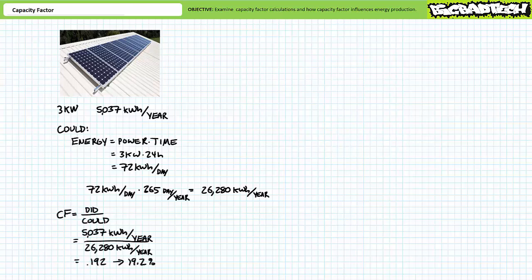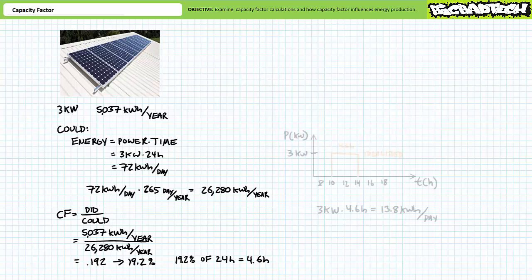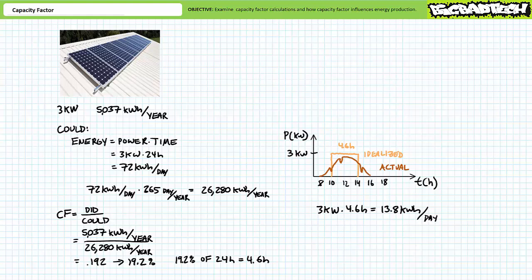Capacity factors did over could. 5,037 kilowatt hours over 26,280 kilowatt hours, its capacity factor of roughly 19.2%. This implies that the solar array produces enough energy as if it did run at full capacity for 19.2% of a day or roughly 4.6 hours. This most assuredly does not mean that the sun immediately rises and shines at full intensity for roughly 4.6 hours and it immediately sets, but rather the sun shines with varying intensity for varying periods with varying cloud cover such that it ultimately produces an equivalent amount of energy as if it did shine at full intensity for only 4.6 hours a day.